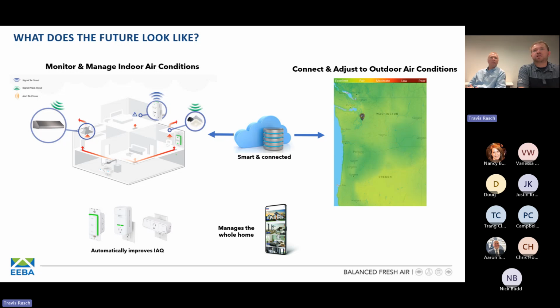And that's where you can get that next piece. What the system does is monitor outdoor air conditions to determine, hey, this might not be a good time to be bringing fresh air in through my supply fan or my ERV. So it utilizes outdoor air quality APIs, interconnecting those to make better decisions on when is the right time to introduce that fresh air, based on real-time measurements of outdoor air quality. So that's kind of where we're at as it relates to what the future looks like. And again, these types of products and this technology are out there already, really to help bring everything back together in managing indoor air quality and ultimately lending itself to a better quality of life.